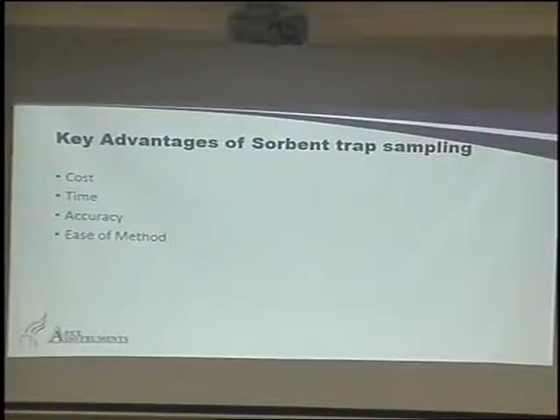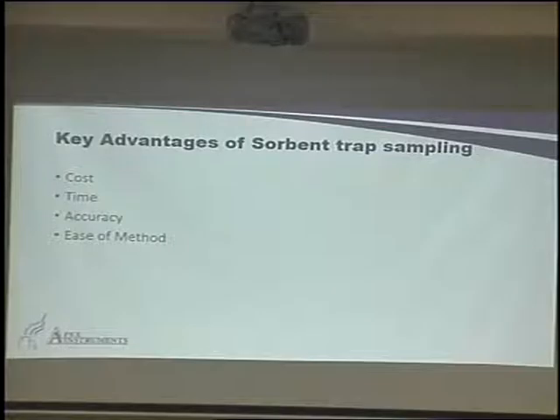So what you would typically do is do 12 complete paired runs of about 30 minutes each. So taking into account changing traps and doing some pre and post leak checks, you'll probably be looking at maybe 8 or 9 hours to do 12 runs, 24 traps total, okay? Then you can plot all 24 or sets of 12 on a graph, and you can discard the 3 outlying ones. So you're going to report 9 sets of traps or 18 traps completely, okay? You could get that done in a day, okay? 30 minutes a run, 15 minutes a change, you're looking at 45, a solid 9 or 10 hour workday, but you can complete that.